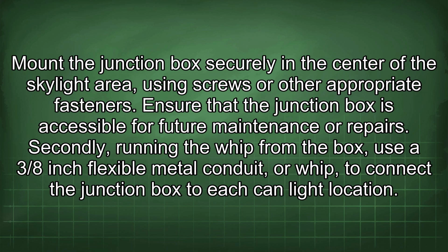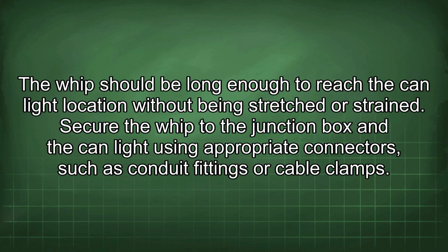Secondly, running the whip from the box. Use a 3/8-inch flexible metal conduit, or whip, to connect the junction box to each can light location. The whip should be long enough to reach the can light location without being stretched or strained. Secure the whip to the junction box and the can light using appropriate connectors such as conduit fittings or cable clamps.